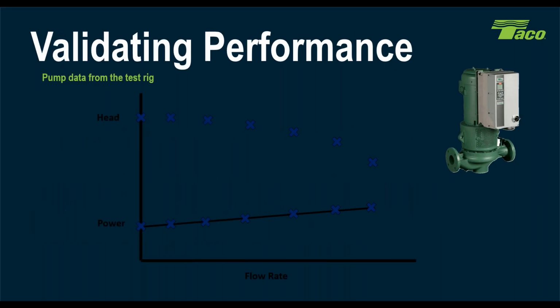So how do we develop self-sensing? Well, first of all, we have to validate the performance of the pump. So we put it on a test stand, and this is similar to developing a pump curve. But what we're actually going to do is take the pump and put it on a test stand, and across the entire curve range, we run the pump out and decrease the head and increase the head and figure out what the power consumption is at each one of those data points. Because we know that for every flow and every head at a given speed, there is a different power requirement. So we map all this out, and that becomes the performance map for the pump.